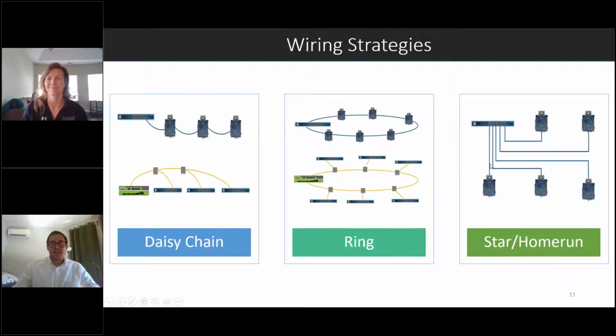Yep. So PoE, that's a great point. You do need to be able to get that power to each individual controller, and the only way you can really do that is leveraging this star home run strategy. But it is a really good strategy if you have something like an old pneumatic system and you don't want to bring in a Division 26 electrical contractor and a BAS contractor, one running power, the other running communication for every VAV box. If you're just going to do a pneumatic retrofit, something like that, you do have the ability to do these PoE switches with power over Ethernet controllers. So pretty cool, interesting use case there.